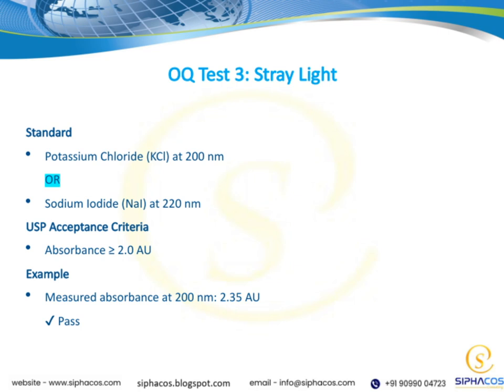For example, if we measure 2.35 at 200 nanometers, that's well above the threshold, so we'd consider that a pass. This test is crucial because stray light can interfere with our measurements, and ensuring the instrument performs correctly at these levels helps us maintain accuracy and reliability in our results.